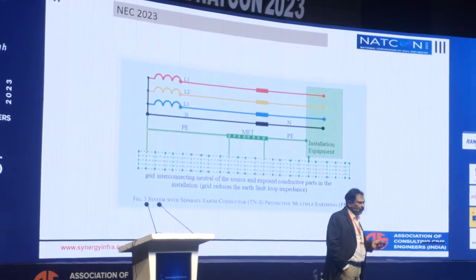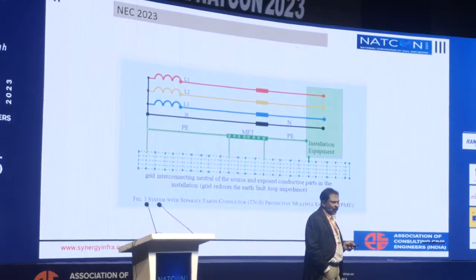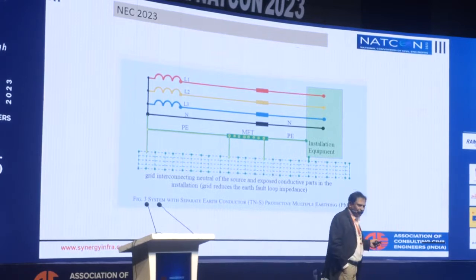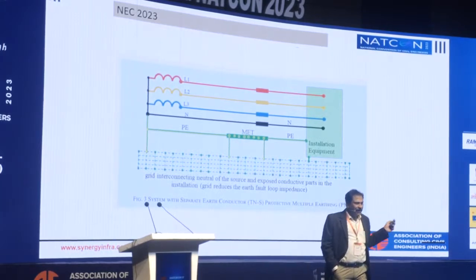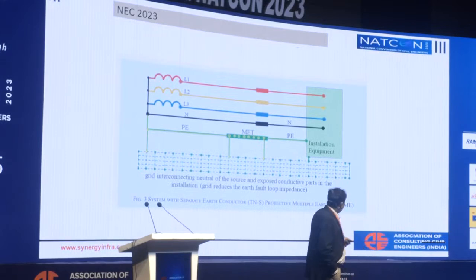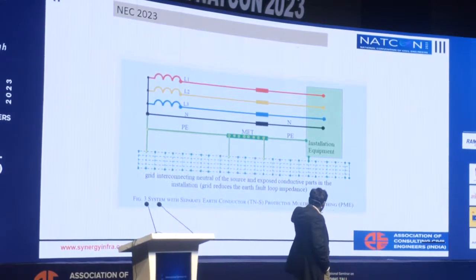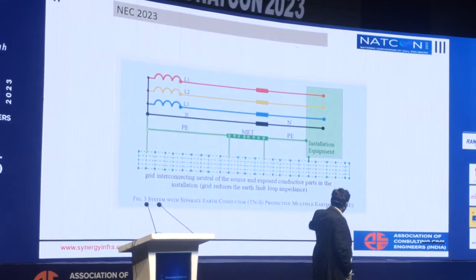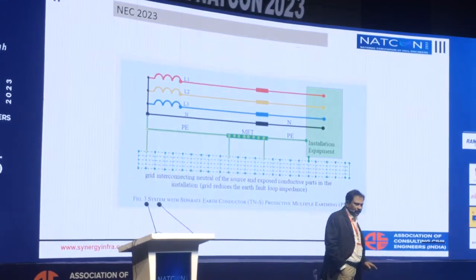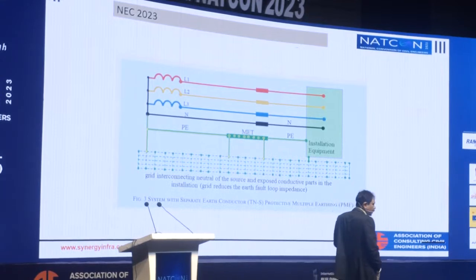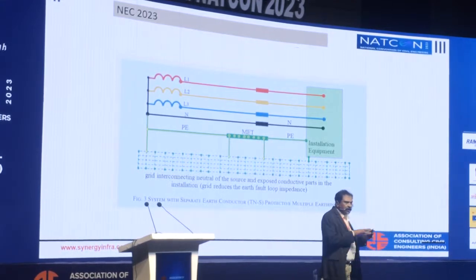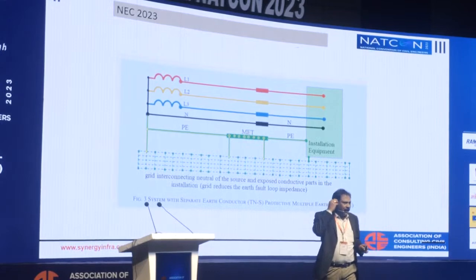This is how the new National Electrical Code is. In fact, we have been practicing this for quite a number of years, but every time we face problems with the electrical inspector. Now we are happy that this is part of the National Electrical Code 2023, where the grid of the entire building, whatever the reinforcement of the basement, is supposed to be connected to the main earthing terminal, and there are not supposed to be a number of earth pits like we used to do earlier.